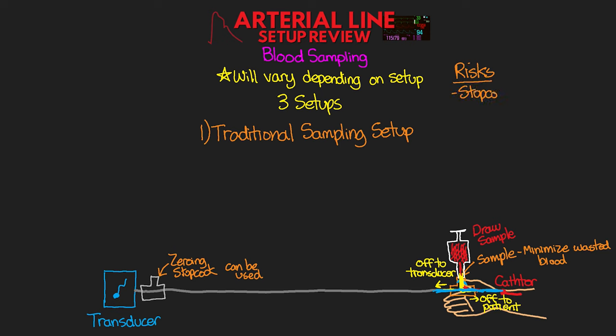First, any stopcock is at risk for being moved or aligned improperly. So this can impair the reading that you get, but more importantly, this could allow blood to flow out from your patient. And massive exsanguination can happen pretty quickly this way. And so remember, the way that the handle is facing out to is where it is off. And so we want to have the handle facing towards the open port when it's not in use.